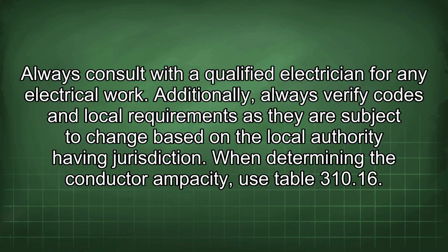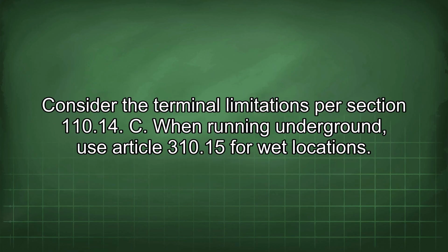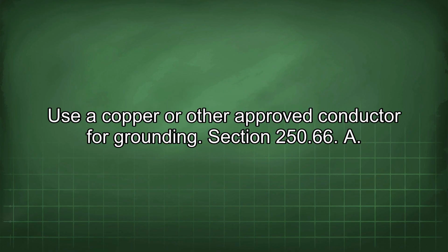When determining the conductor ampacity, use Table 310.16. Consider the terminal limitations per section 110.14(C). When running underground, use Article 310.15 for wet locations. Use a copper or other approved conductor for grounding.